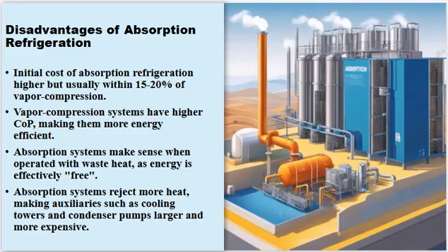Efficient heat utilization. These systems can effectively utilize waste heat or renewable energy sources, enhancing their efficiency and sustainability. Disadvantages of absorption refrigeration. Higher initial cost. Absorption refrigeration systems have a higher upfront cost, typically about 15 to 20% more than vapor compression systems.